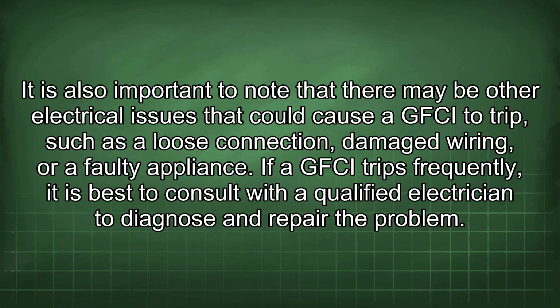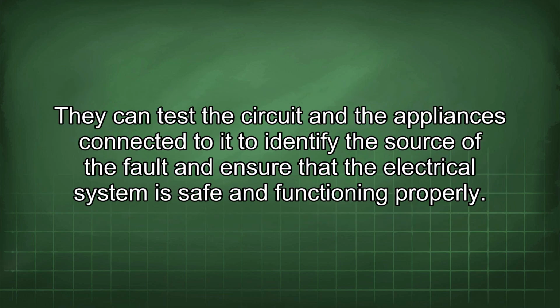It is also important to note that there may be other electrical issues that could cause a GFCI to trip, such as a loose connection, damaged wiring, or a faulty appliance. If a GFCI trips frequently, it is best to consult with a qualified electrician to diagnose and repair the problem. They can test the circuit and the appliances connected to it to identify the source of the fault and ensure that the electrical system is safe and functioning properly.